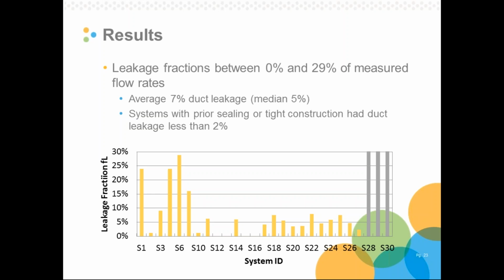So in other words, we have a lot of systems that leak a small amount and a few systems that leak a big amount. We also found that systems with prior sealing or tight construction were generally very tight. They had leakage rates less than 2%, and they helped to bring down this number.